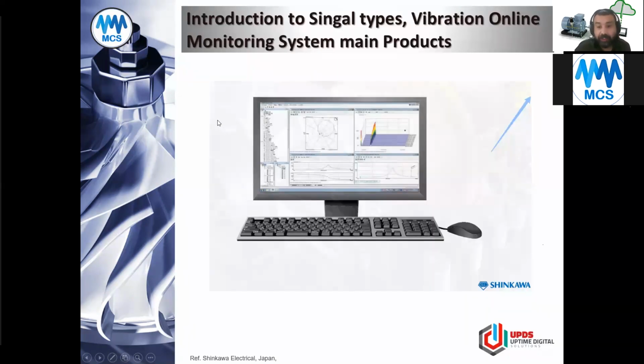Right. After I finish all of this hardware selection and build my system, I need to build something we call an IO list. In this IO list, I take every single sensor I have on my machine. It has a name, and I need to configure it in software. You have two types of software, and don't mix them up: analysis software and configuration software.